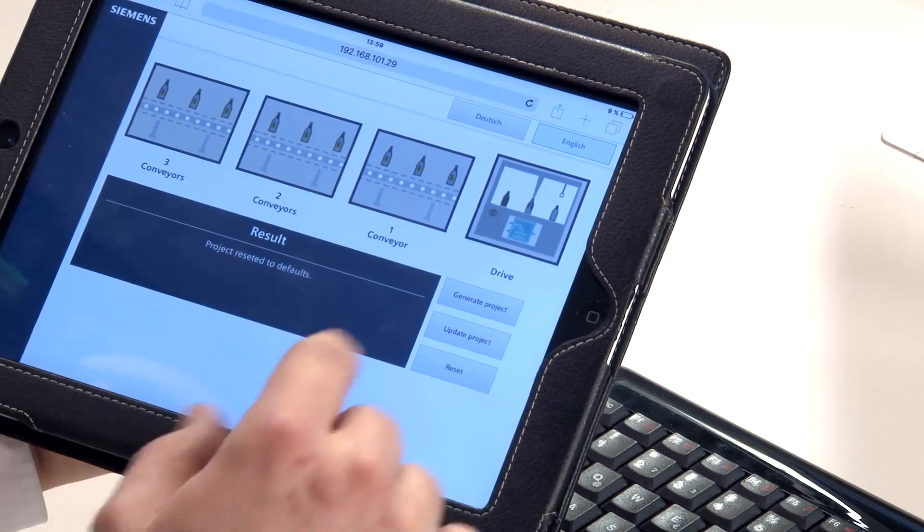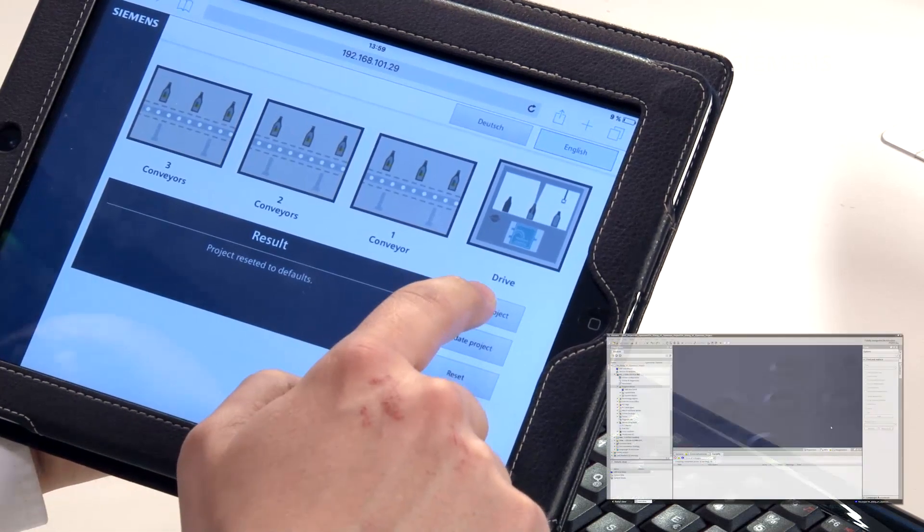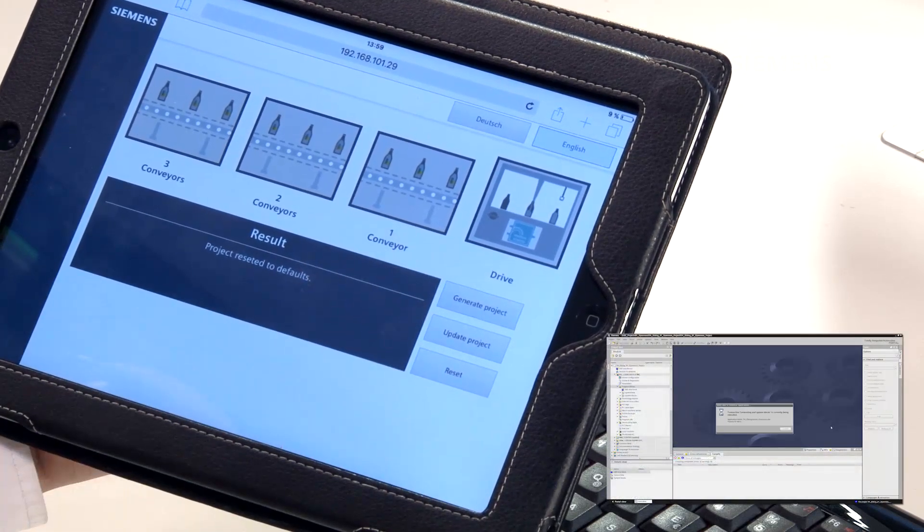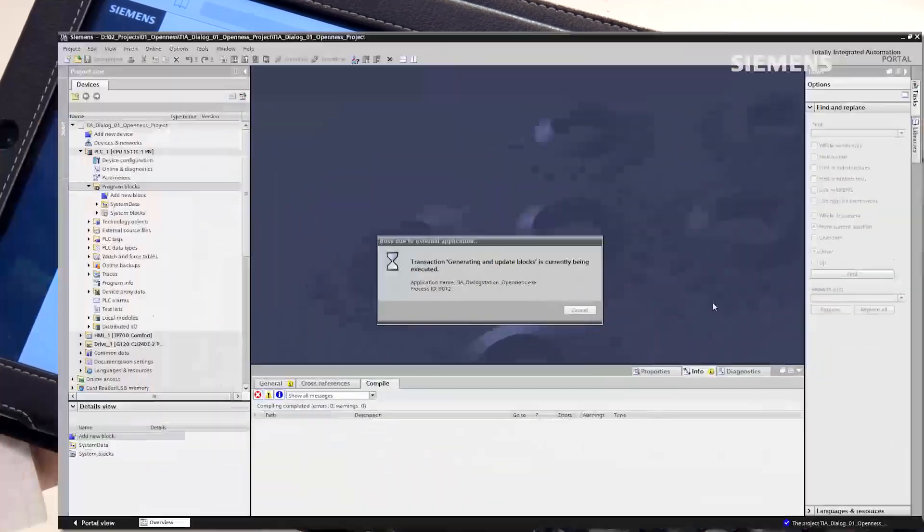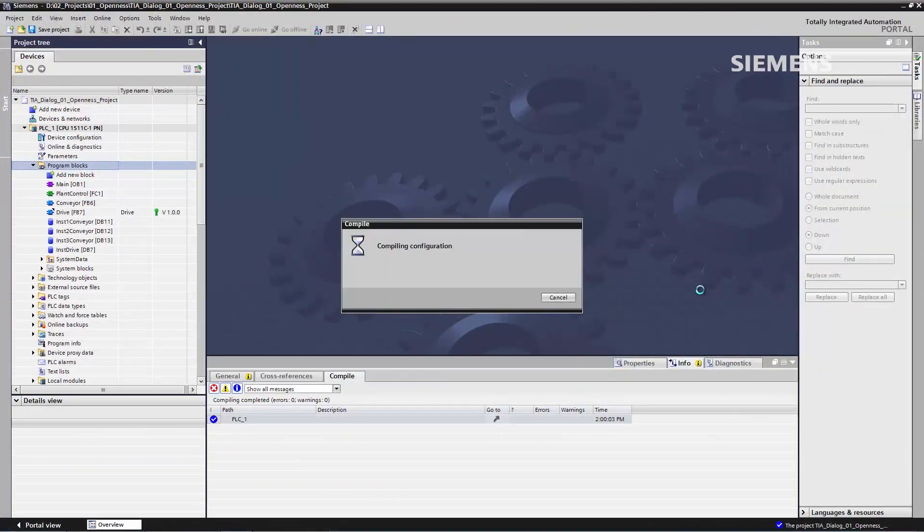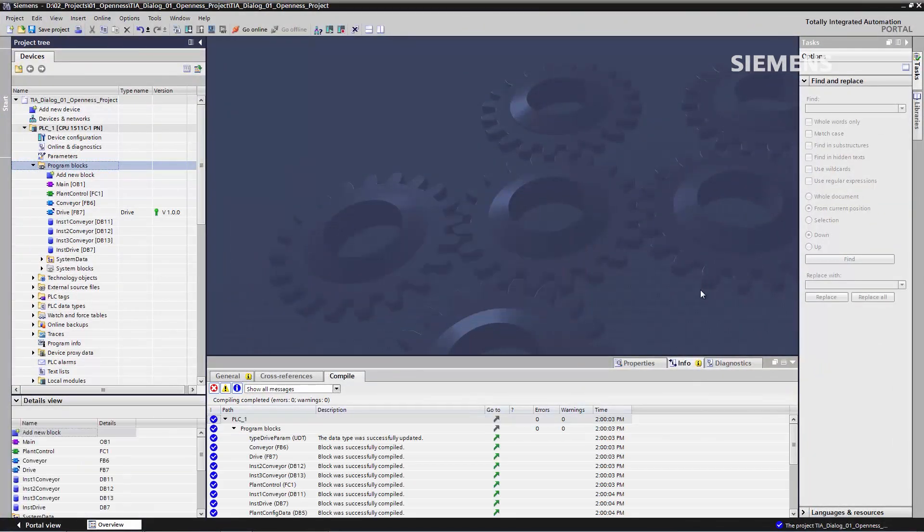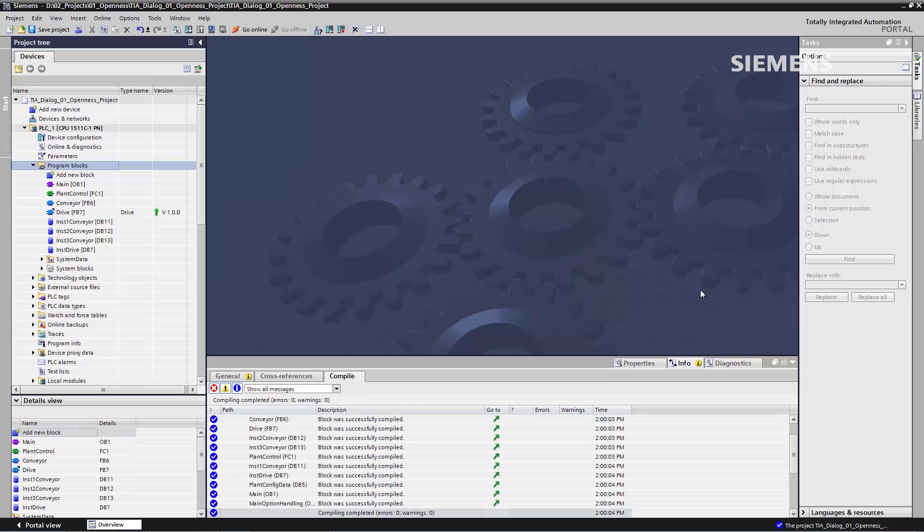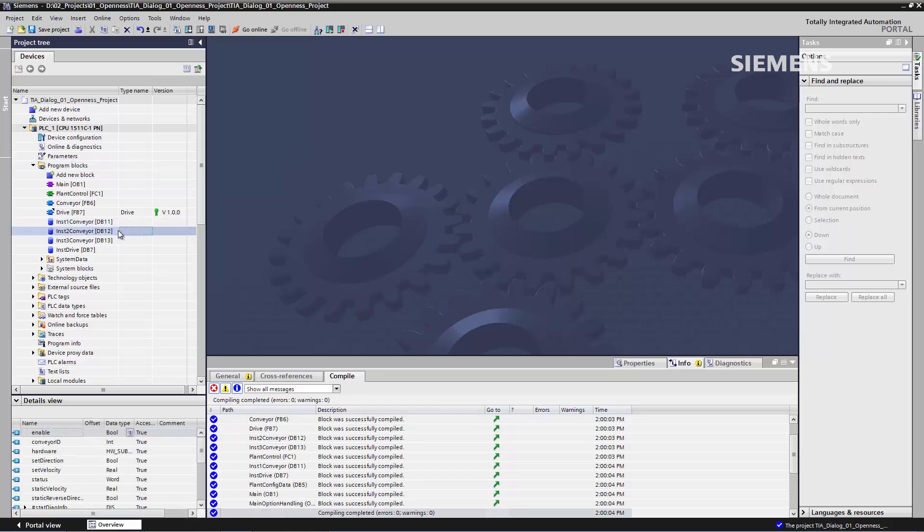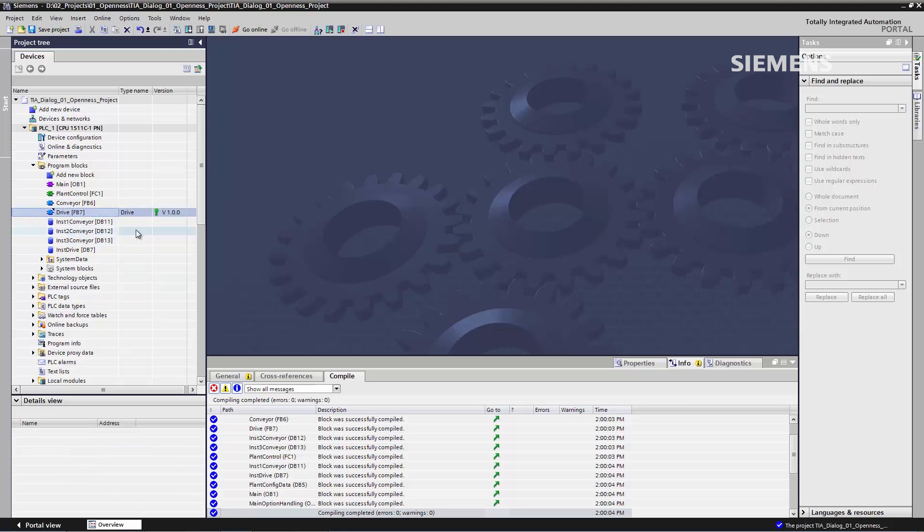It is also possible to activate and deactivate a drive. With the click on the button Generate Project, we can integrate this project into the TIA Portal, and with one additional click you can see how these modules appear in the TIA Portal. We now have three instances of the conveyor belt block, as can be seen here, and an additional instance of the drive block.